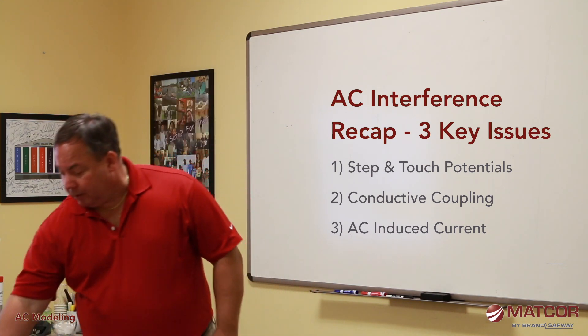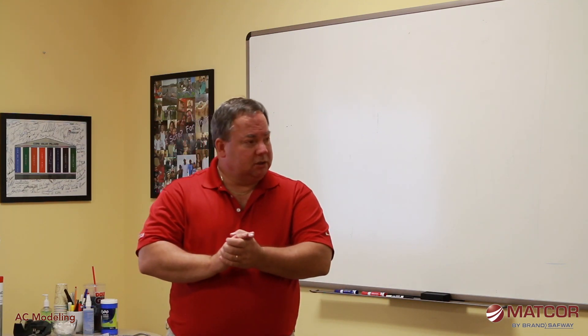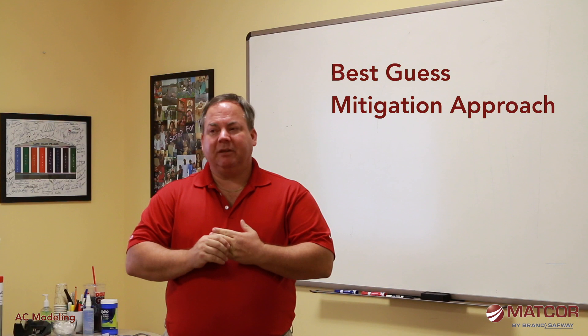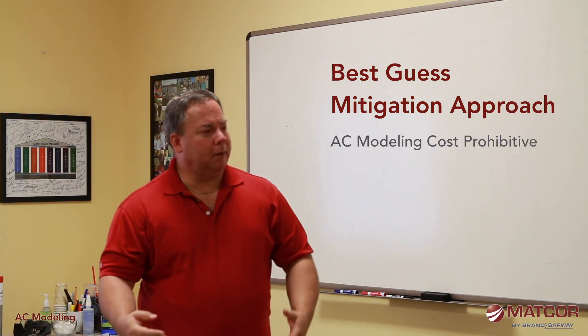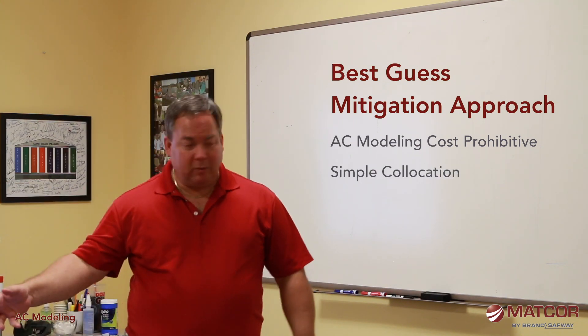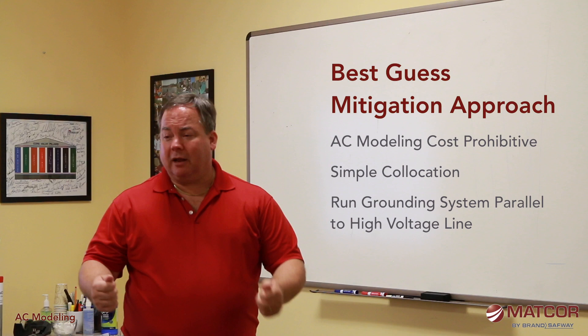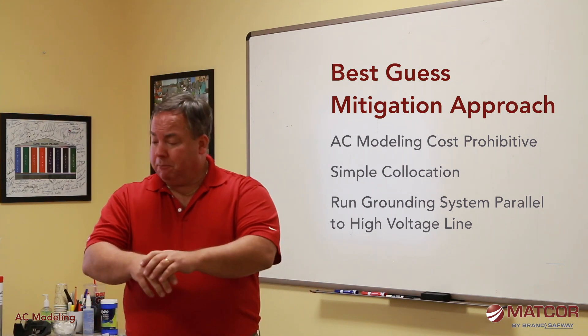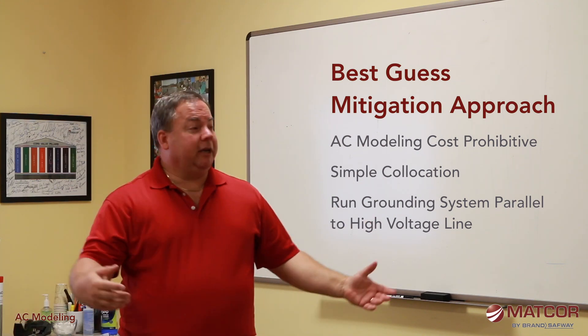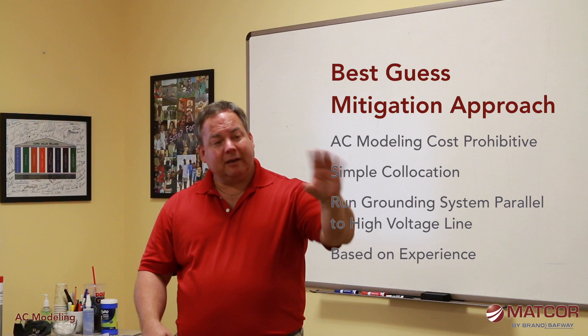In some instances we can do a best-guess mitigation approach — it's just not worth the effort to put everything into a model. For example, a simple one-mile co-location where the pipeline runs parallel to a high voltage line and then leaves — I've measured AC pickup and I'm just going to put grounding in from A to B and be done with it. It's over-designed, but the cost of modeling would exceed the cost of just fixing it.